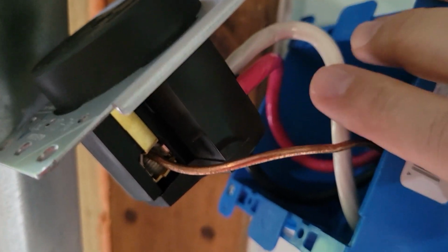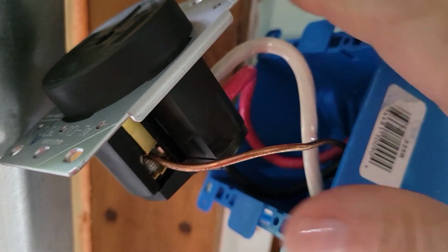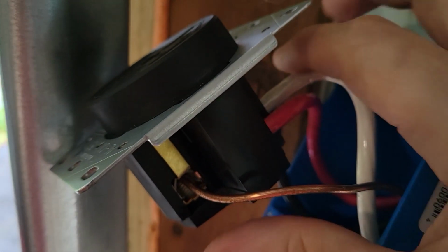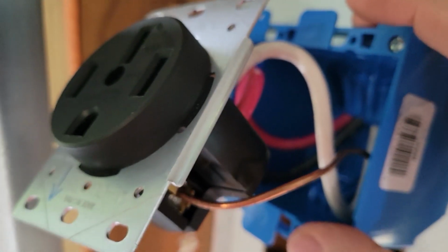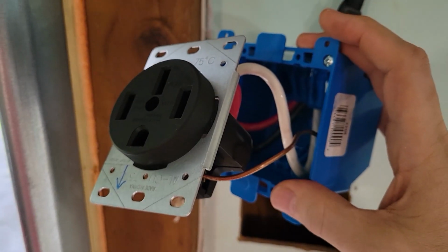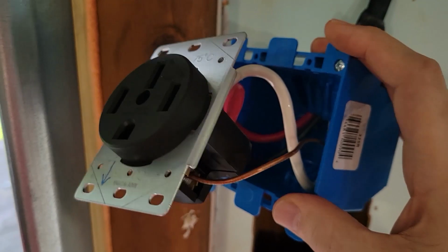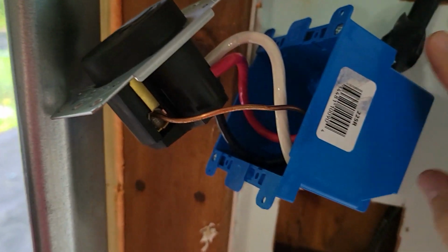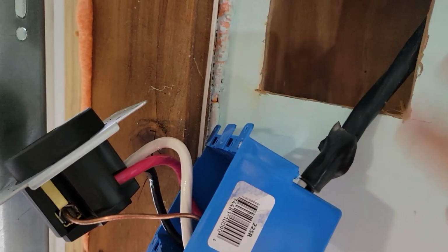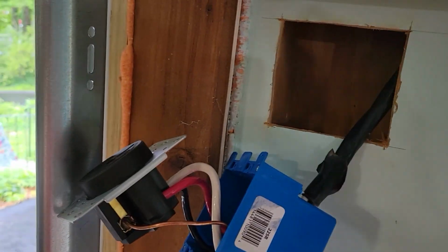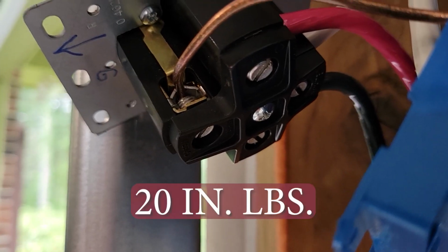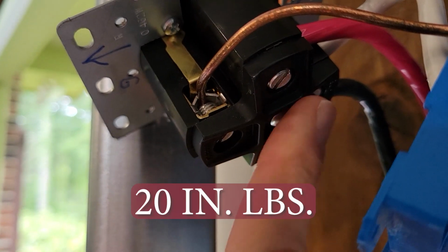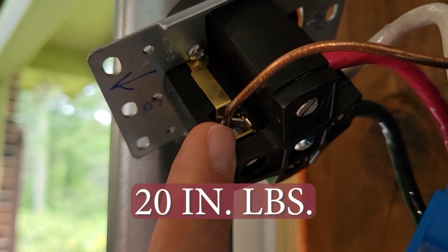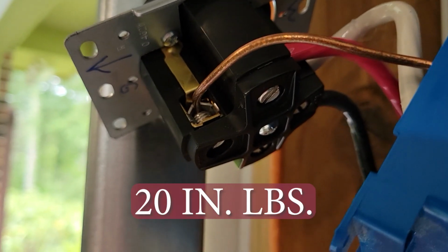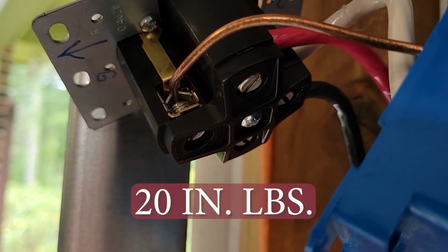Now the big challenge is getting everything back in the box and cushioned up. I have some gradual turns in here, and I'm hoping it'll all go back into the box nice and easy. Once that's in there, getting this into the wall should be fairly easy, and then we put on our wall plate. Don't forget, each of the fasteners has to be torqued. Specifications for this receptacle are 20 inch-pounds for each fastener, including ground.